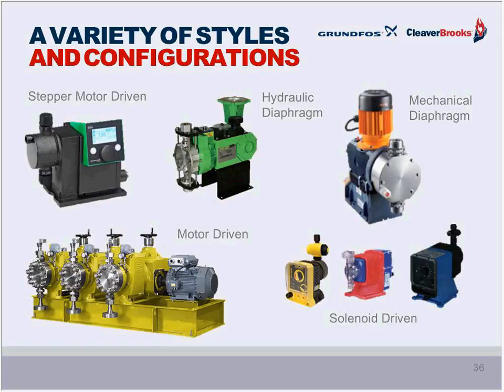So there are different types of dosing pumps that exist in the market today. Historically, many different solutions and diverse technologies evolved to solve specific problems in steam boilers. Many concepts are available. At the top of the screen is a green pump, a hydraulically actuated diaphragm pump. Next is one with an orange motor, which is a mechanically actuated pump. Then there's a multi-head pump with a common motor, which is good for multiple injection points, mixing chemicals, or even just increasing the flow rate. Also at the top of the screen are some typical solenoid-driven pumps, which typically have low flow rates and are very common in the market today.